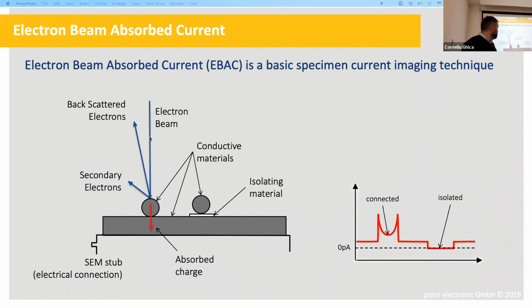So, for example, if that's our electron beam, then we will have backscattered electrons and secondary electrons, and we are really now referring to absorbed electrons, which historically has been defined in the old literature as charge. So we are absorbing charge into the sample, and that forms a current which we then measure, as simple as that. It's very straightforward, and that's why it was discovered very early on, and it's very useful if you develop instrumentation. But it's slow because the amplifier cannot be as fast as an in-lens detector or in-chamber detector. So historically it's been put to one side and overtaken by better, faster detectors. But it will give us an image.